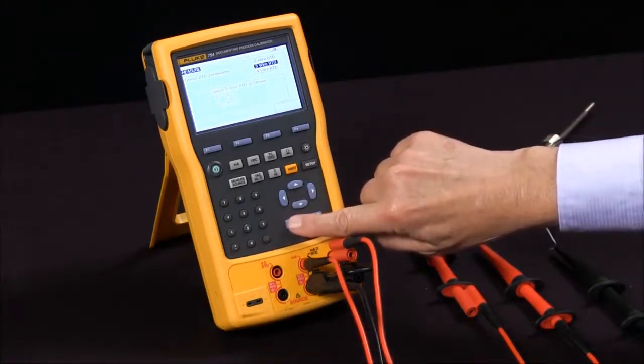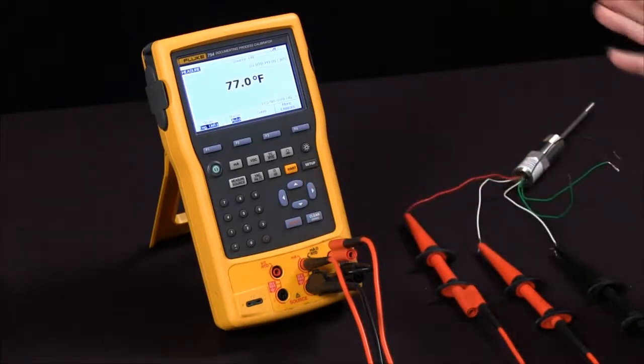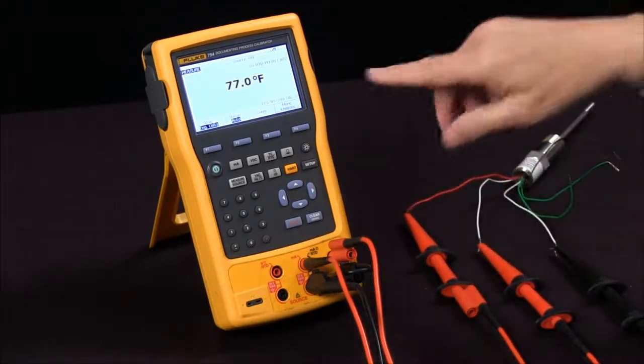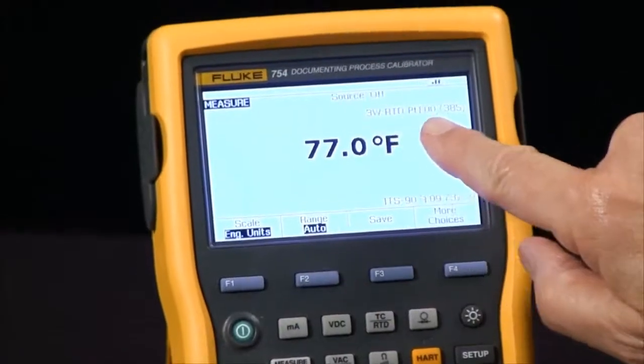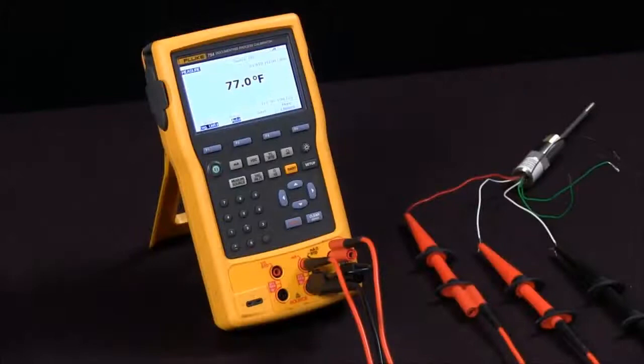So I select three wire and it goes in the measure screen and it measures the RTD that's measuring room temperature here at 77 degrees Fahrenheit. So you see on the screen it says three wire RTD Platinum 100 ohm 385. And that's how we measure an RTD.